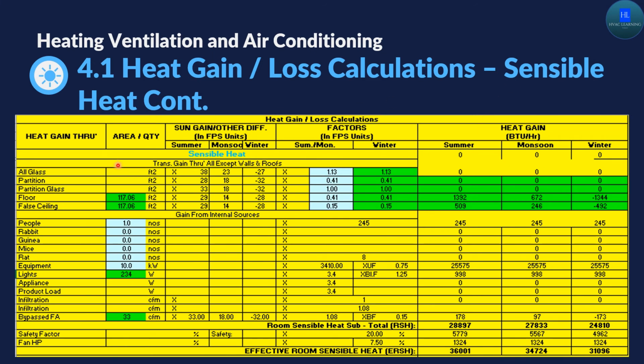In the next portion, the next addition of heat gain is from the false ceiling or the adjacent areas, from the people, from the animals if it's an animal facility, from the equipment, from the lights, or some of the air which will pass through the cooling coil without being dehumidified. Let's say the cooling coil has an efficiency of 70%.